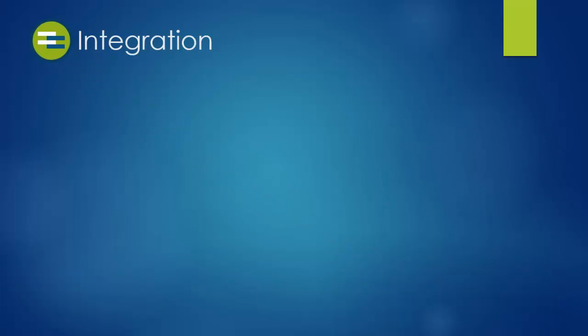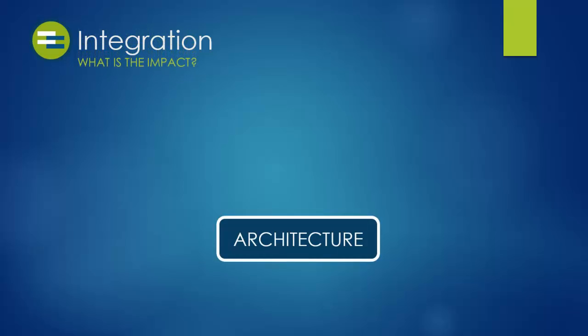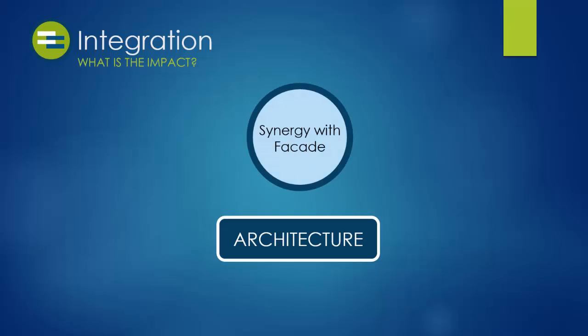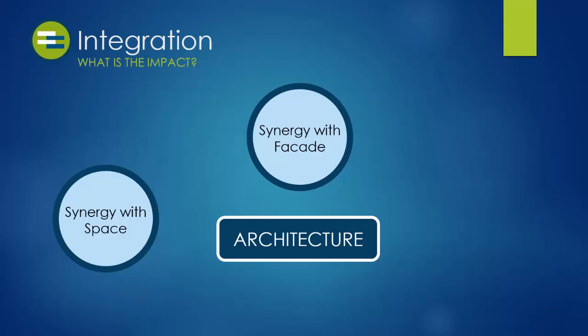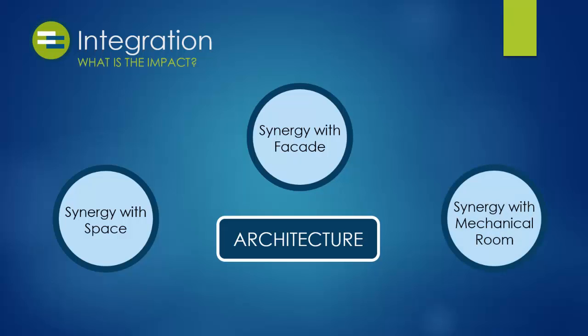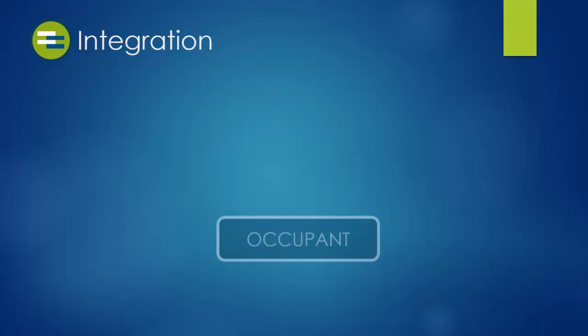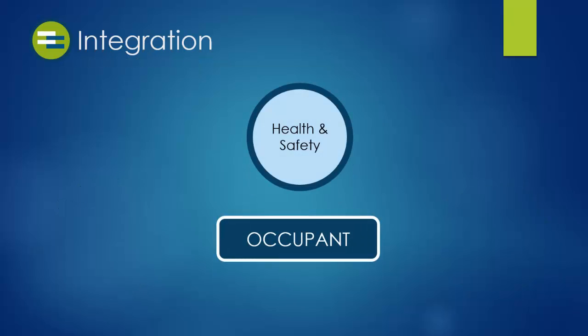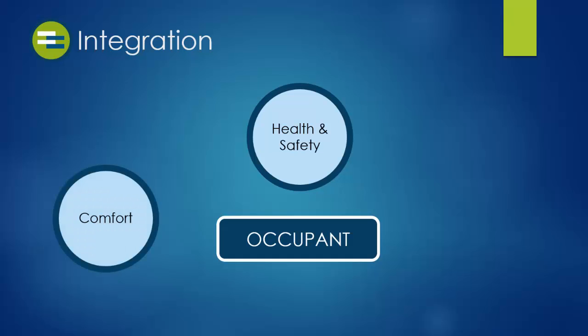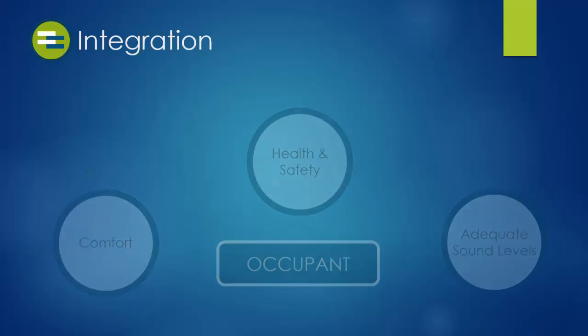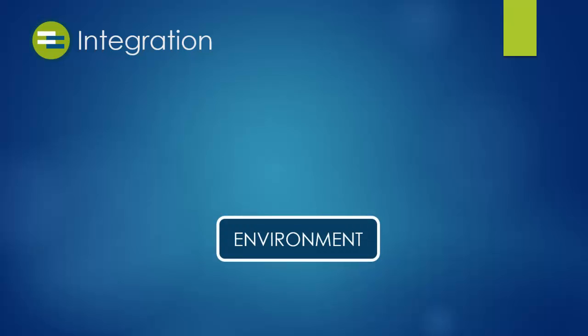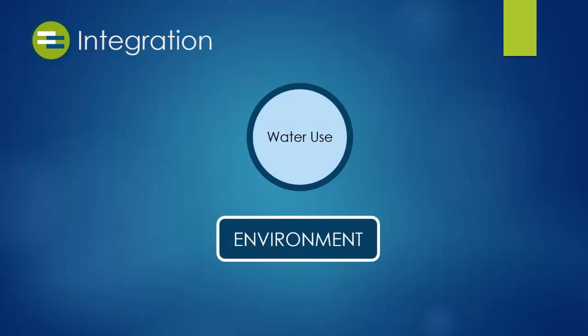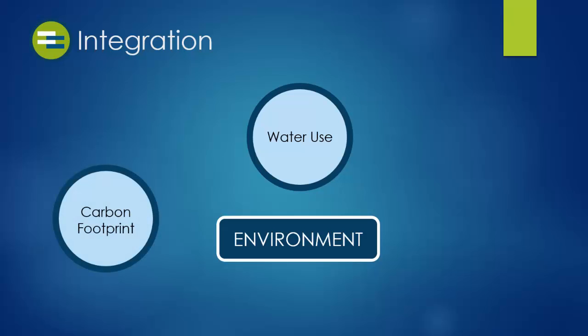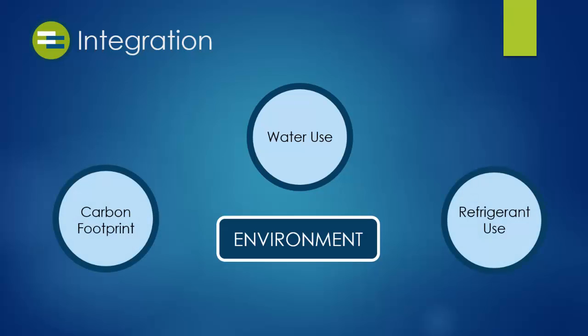An ideal system should integrate well with the architecture, occupants, and environment. Architectural integration is achieved by the ground source heat pump system by integrating well with the exterior facade and the occupied spaces, and by decreasing the required space needed in the mechanical room. The ground source heat pump system integrates with the occupants by providing a healthy and safe environment, allowing for maximum comfort, and providing optimum sound levels. To integrate well with the environment, the ground source heat pump system decreases water use and carbon footprint and complies with ASHRAE Standard 15 for refrigerant use.